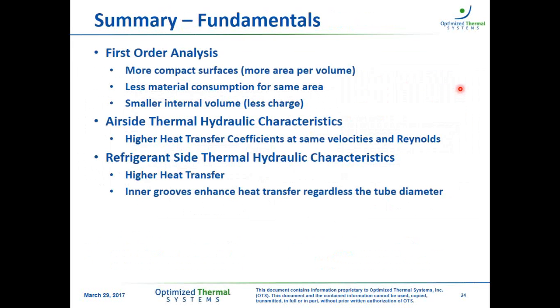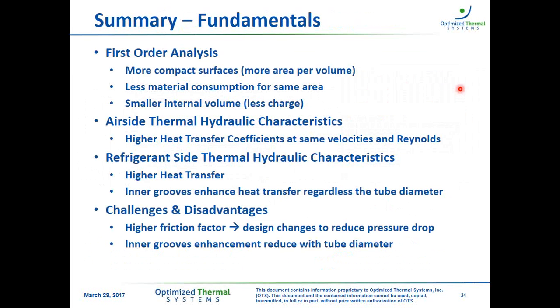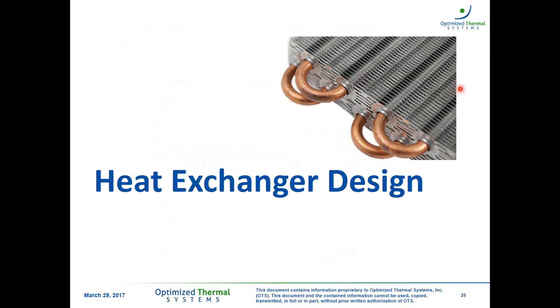On the refrigerant side as well, the micro grooves have enhanced heat transfer regardless of tube diameter, so we can all benefit from it regardless if it's 3 or 9 millimeters. But now, some of the challenges and disadvantages. As we saw, for both sides, we have a higher friction factor, so this poses some additional design challenges so we can actually reduce the pressure drop on both working fluids. And the micro grooves enhancement reduces with the tube diameter, though they're still beneficial. They're not as good as they are for larger diameters. So these are some of the considerations.